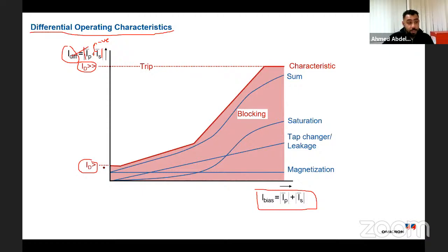And in the area between ID greater and ID greater greater, I have a characteristic with slope equal to 0, or we can call it the flat region, then slope number 1, slope number 2. So you can see it's a line, it's a segment, and it has two slopes, slope S1 and slope S2. And we define the area under slope 1 and slope 2 as the blocking area, and the area above slope 1 and slope 2 as the trip area.